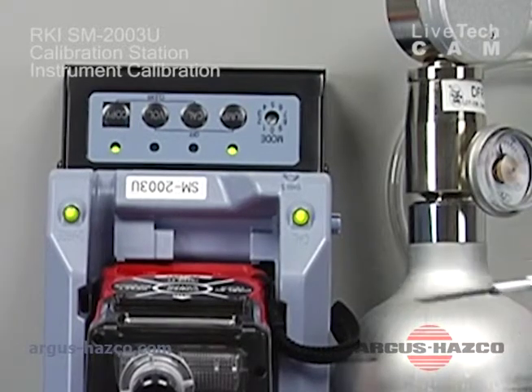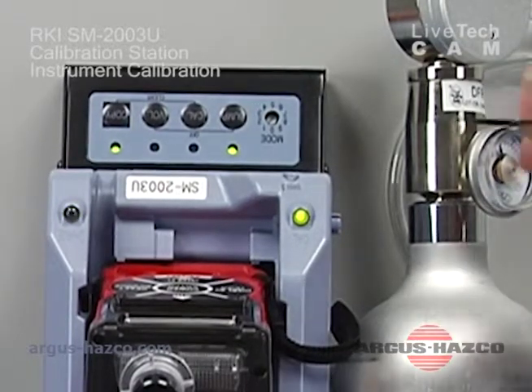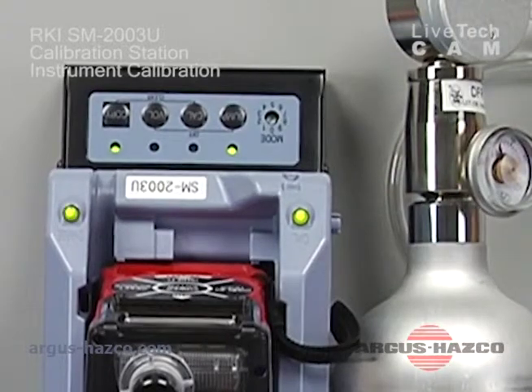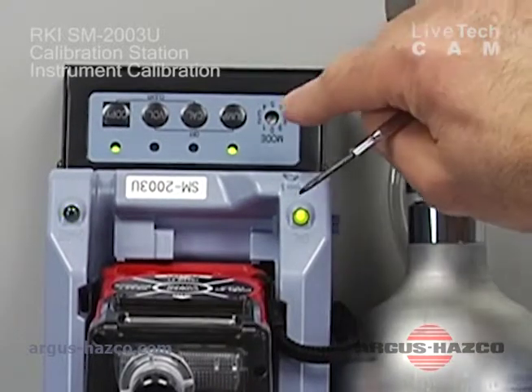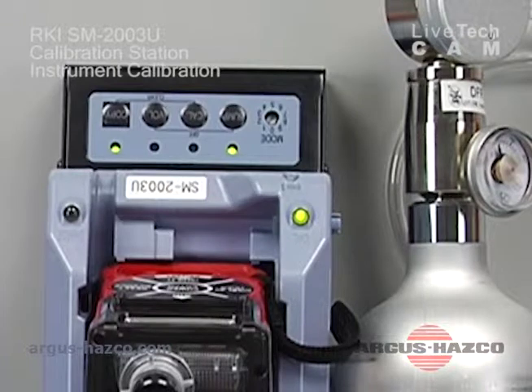The way to identify if it has passed is that the amber light that was flashing will turn to a solid green, and the light above the bump or cal, whichever function you choose, is a solid green as well. That means that function has completed. Now, this obviously has passed the bump test. If it were to fail, it would immediately go to cal, and then you'd see the cal button flashing, or should I say the light above the button start flashing to indicate that that function is in operation. Okay?